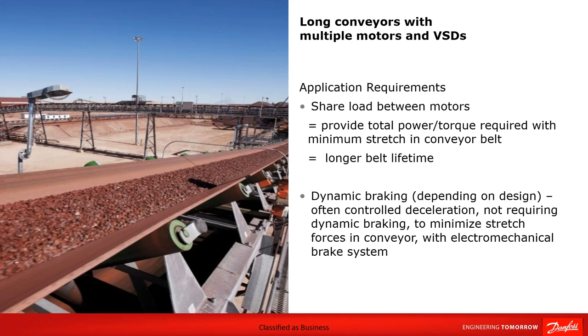Application requirements: we're sharing the load between the motors, providing the total power and torque required with minimum stretch in the conveyor belt. Remember, we don't want to stretch the belt so that it breaks. What does that do? It gives us a longer belt lifetime. And then dynamic braking, well, that depends on the design. Often controlled deceleration is used, not requiring dynamic braking, to minimize the stretch forces in the conveyor, with the electromechanical type brake systems.